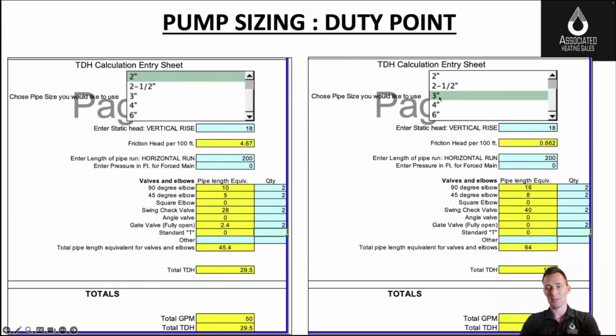If you simply ran the system in 3-inch pipe, 4-inch pipe, you have very little friction. For each 100 feet there, you're going to add 0.6. So you're really only adding 1.2 on the horizontal. You add some fixtures here, so elbows, check valves, isolation valves, adds very little. Most of your head is going to be that vertical component. Add a couple feet of head for the horizontal, but look out for this 2-inch run. This is going to add quite a bit. This is at 50 gallons a minute. So as you go up in gallons per minute, you may see even more head being added.